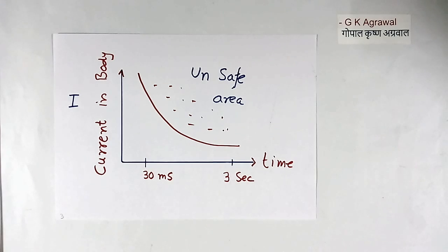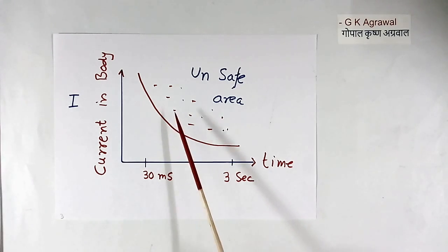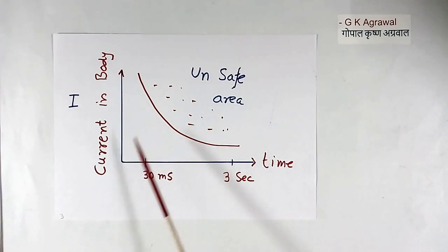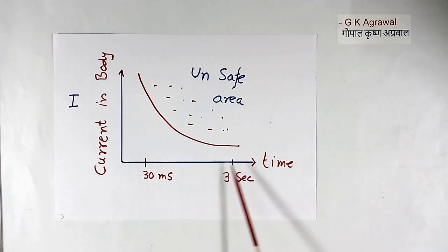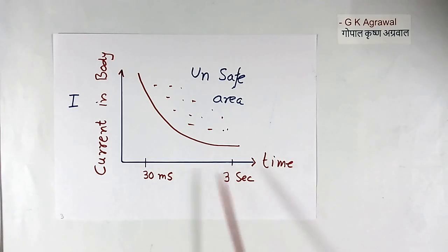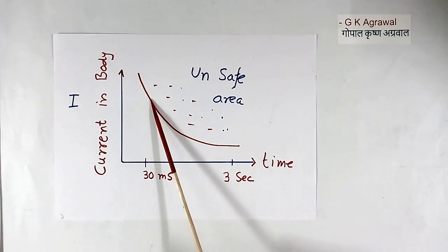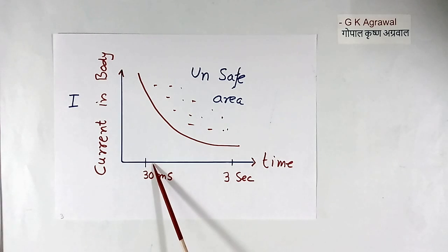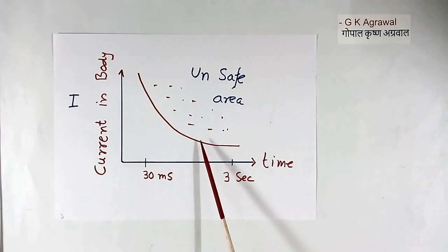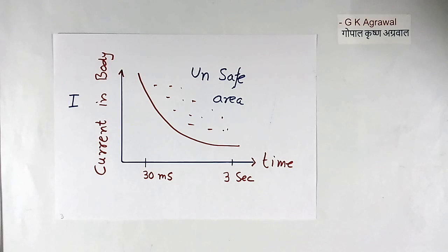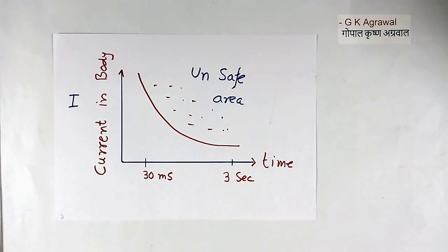How much current can a body take safely? This is shown in this plot. The unsafe area is indicated here — this axis is current in the body, and this axis is the time for which current flows in the body. If current is more, then it can flow only for a short time. If current in the body is less, then it is allowed for a longer time. Now, how do we decide whether to select 30 mA or 100 mA for the RCCB?